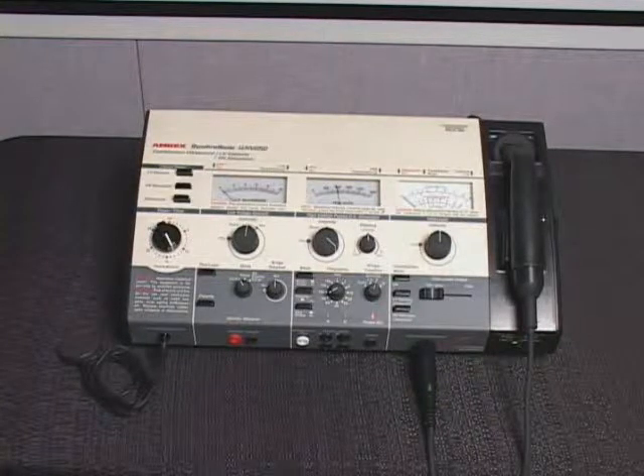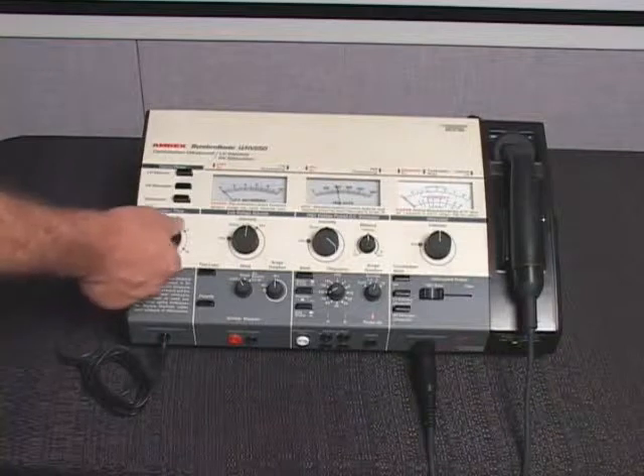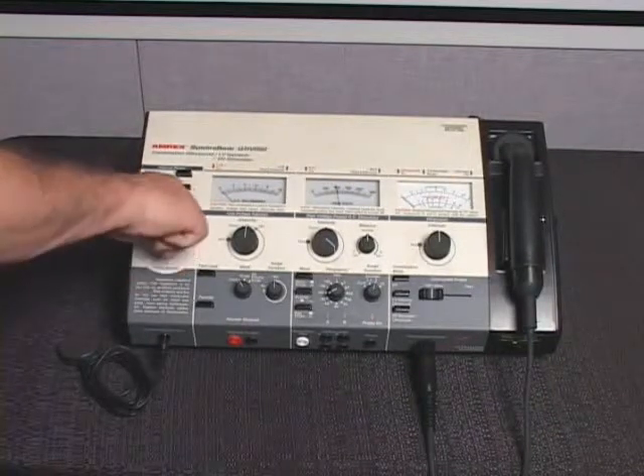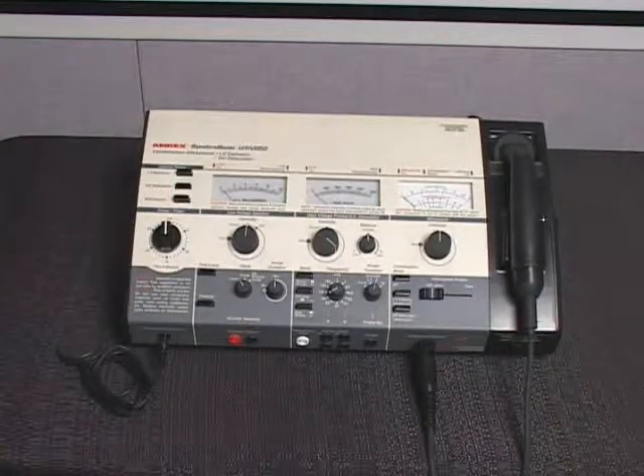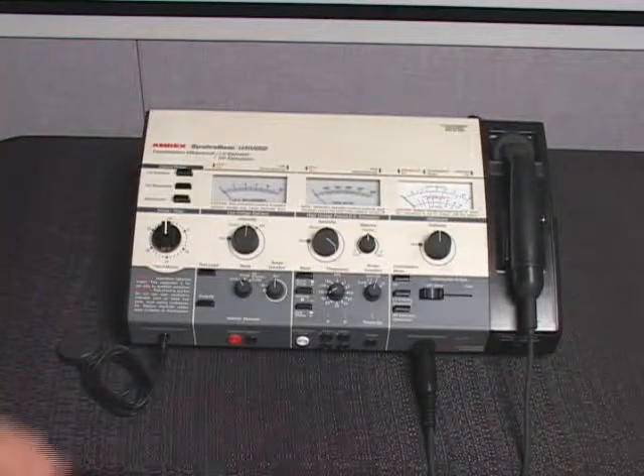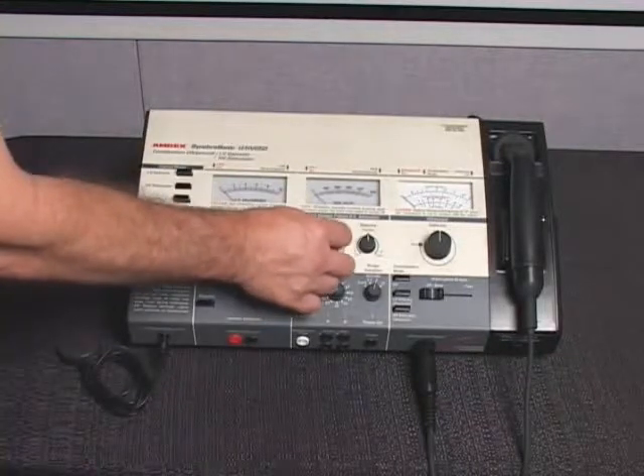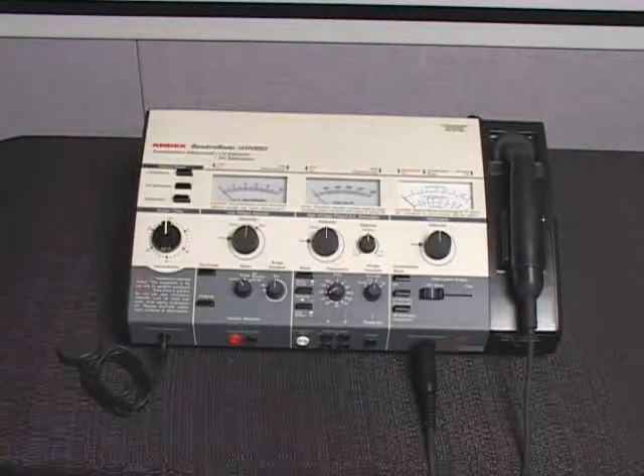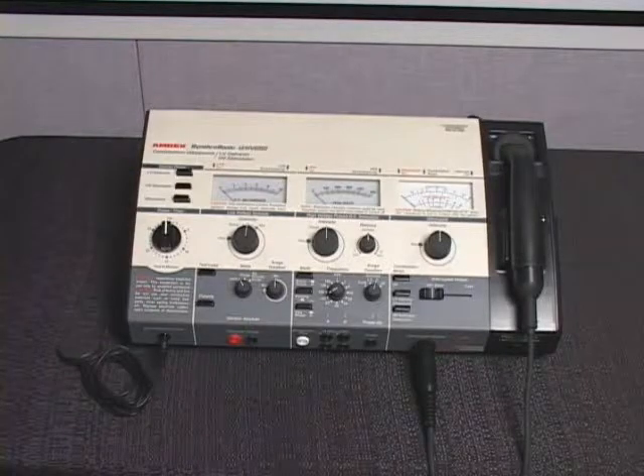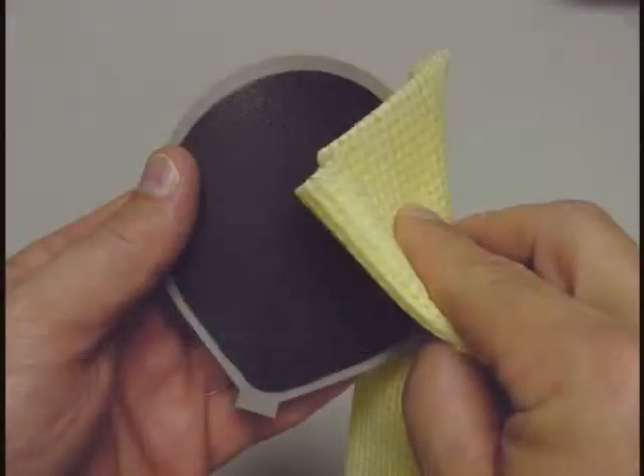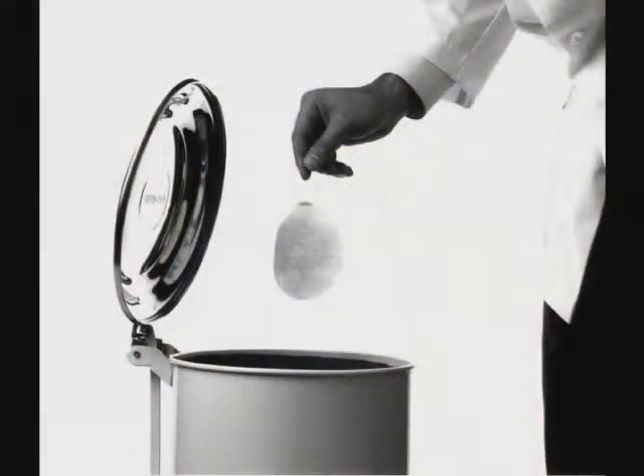When treatment is completed, the AC power will shut off and a bell will sound. To initiate early shutoff, turn the power timer knob counterclockwise to the off position. The AC power will shut off and a bell will sound. Reduce the intensity control to the zero reset position. Thoroughly clean the pad electrode or electrodes with warm water and dispose of the used cloth cover or covers.